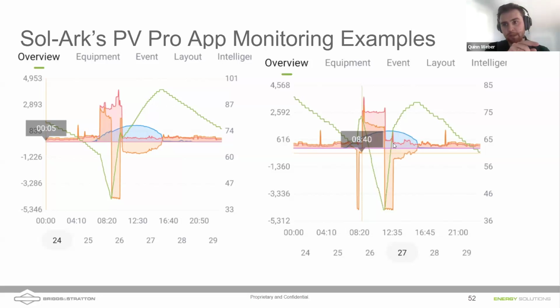You can see the battery state of charge goes down a little bit as it continues to support the well, and then the rest of the day solar recharges those batteries. I wanted to also highlight, this is another day where a very similar thing happened. Battery state of charge got low, so they turned on the generator, recharged the batteries, and turned on his well pump. This time, it looks like he knew he was about to turn on the well pump, so he exercised the generator manually before turning it on. So he had a little bit of juice in his batteries, ran his well pump, depleted the batteries, and then the generator triggered and recharged the battery. I just wanted to demonstrate, this is a customer who's fully off grid, he's been off grid for, I think, 40 years, and this is the first time he's had a system able to automatically trigger the generator and run off the batteries to support his well pump. He likes fiddling with it, but he's very impressed with the system so far.